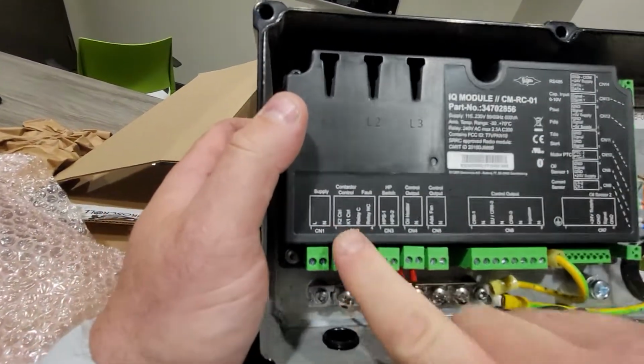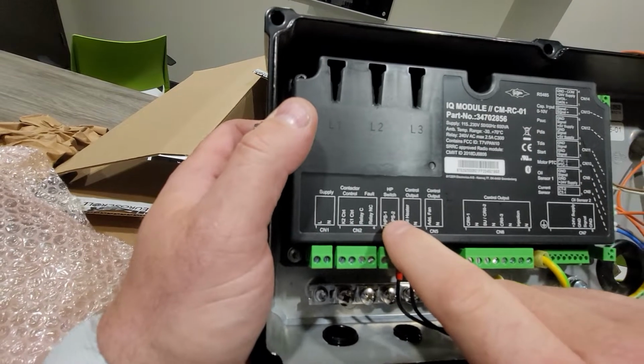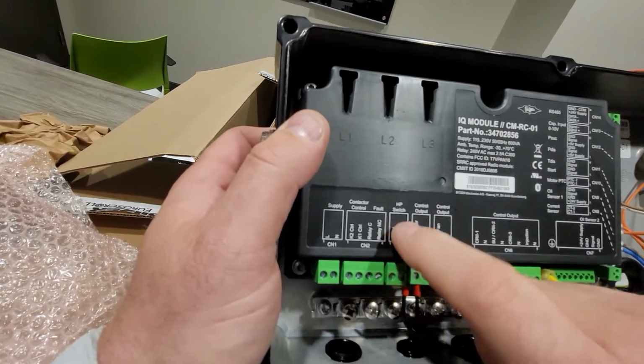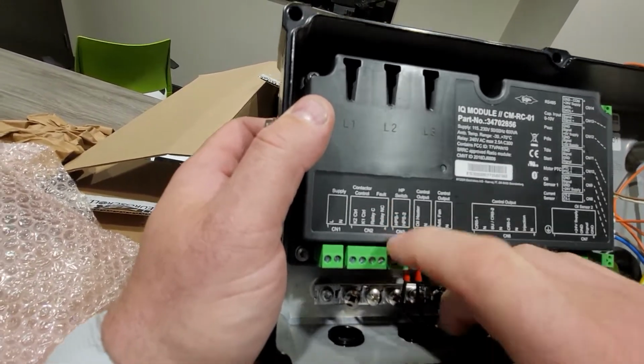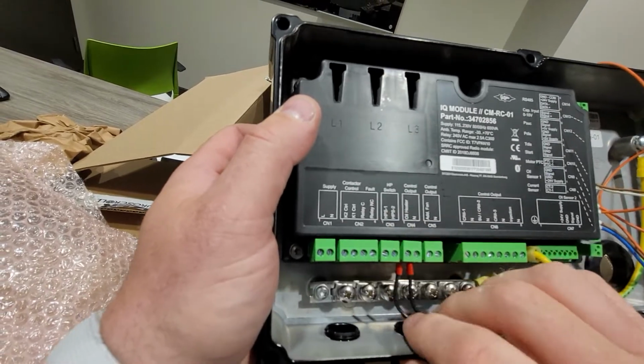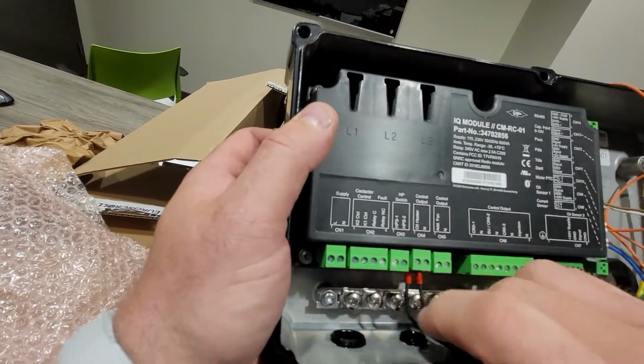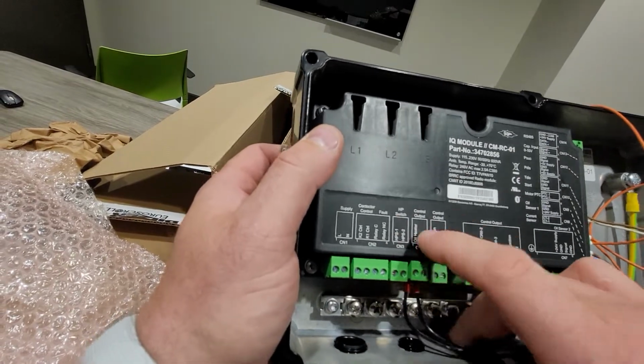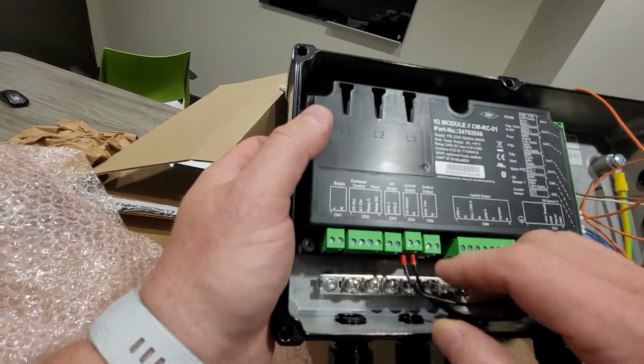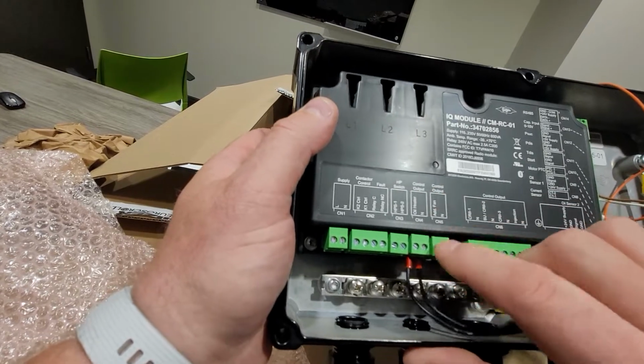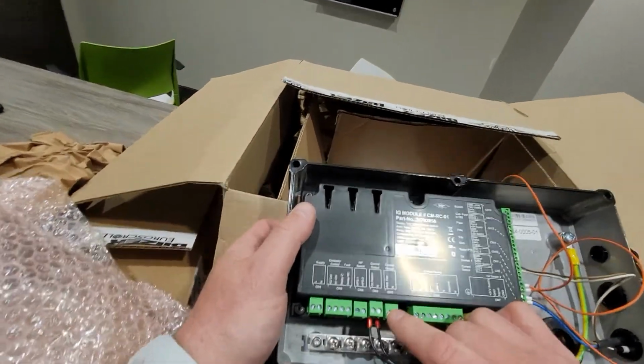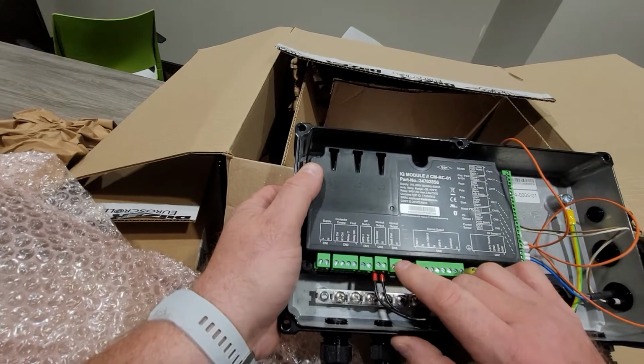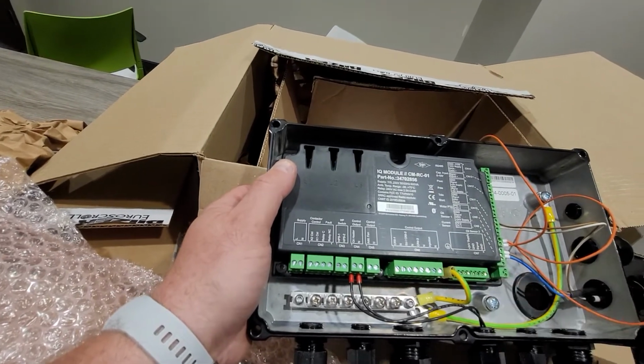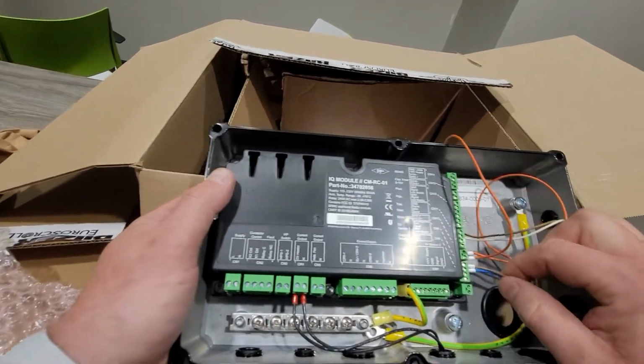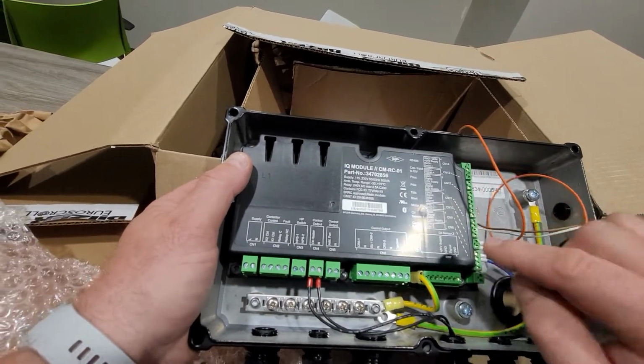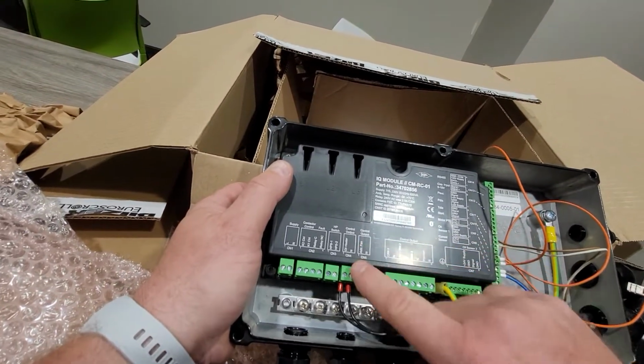In this here, you'll have your compressor controls. Your high pressure switch, which is a mechanical lockout. You need that for lots of reasons, engineers will tell you why. Here's a control output for the heater, which is already wired. Here's a control output for a compressor head cooling fan motor. So when the discharge temperature sensor, which is wired here, sees the discharge is getting too hot, it'll turn the head cooling fan off and on as needed.